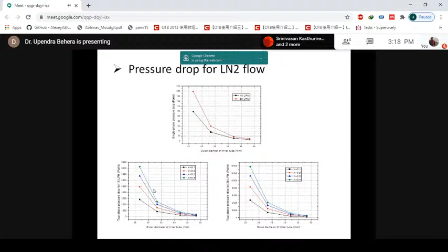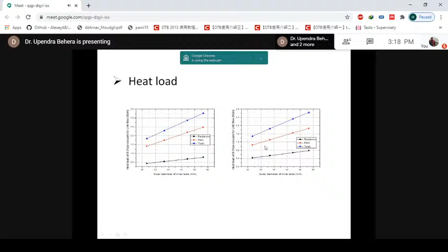Okay, and this is the heat load that we have calculated for a vacuum of 0.1 Pascal for liquid helium flow, and this is for LN2 flow. Here this is the radiation heat transfer, and this is the free-molecular conduction heat transfer. When you add them together, for the 27 mm diameter it is around 0.36 watt per meter. Similarly, for LN2 flow it has come to around 4.2 watt per meter total heat load. And once the pipe diameter increases, the heat load also increases a little.